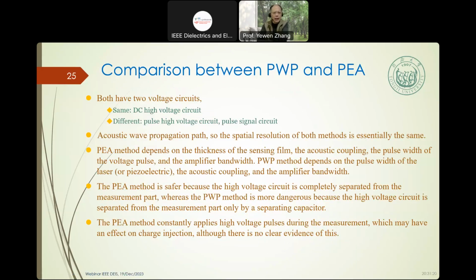So we make some comparison between the PWP and the PEA. There are two voltage circuits with the same applied DC voltage, but they are very different. For the PEA, there is a pulsed high voltage circuit, and for the PWP it is a pulsed laser signal. The acoustic propagation is the same. So the spatial resolution of the two methods is essentially of the same order. The PEA method depends on the thickness of the sensor film, usually PVDF, the acoustic coupling, the pulse width of the applied voltage pulse, and amplifier bandwidth. The PWP method depends on the pulse of the laser or piezoelectric, the acoustic coupling and amplifier bandwidth.